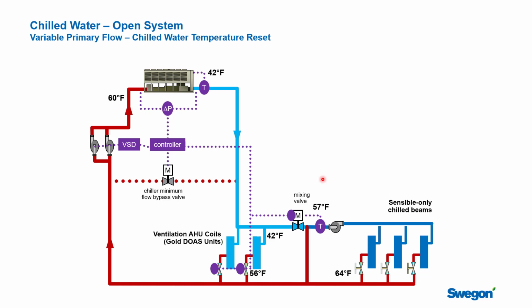But you also have to remember how important it is to have good dehumidification control in your building. Remember that all the dehumidification for the whole building will happen in these air handling units. And so the chilled water temperature really has to be prioritized by the need to dehumidify. If you can dehumidify the air with warmer water, you should do it. But often that water temperature is picked to create a leaving air condition off of these coils to maintain the right humidity level in the space. And so I would caution you to be very careful about this and really think it through before you do it, because you do have to maintain that flow.